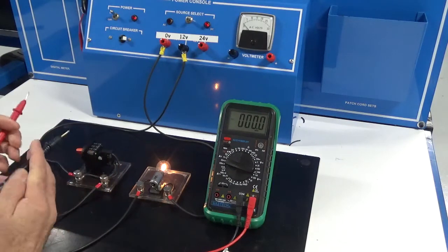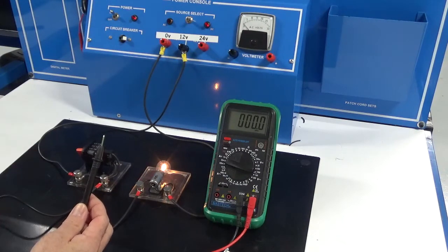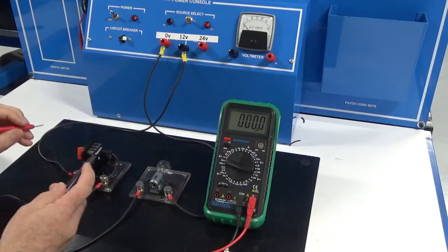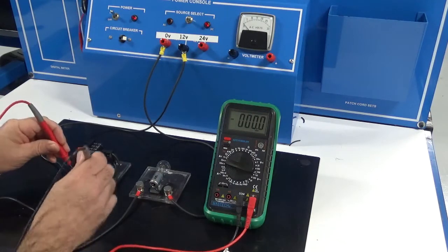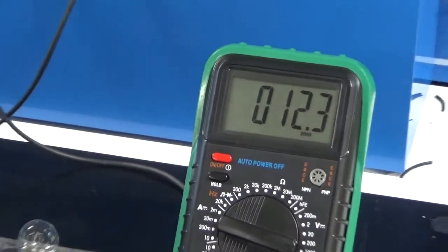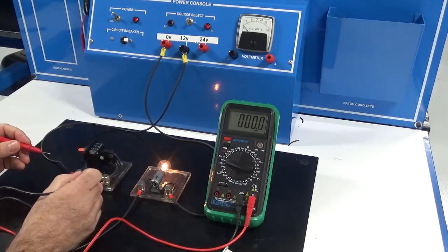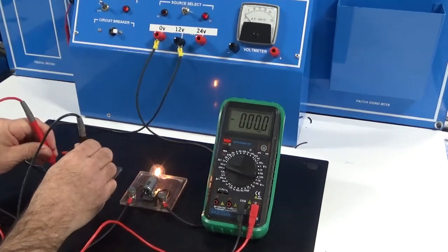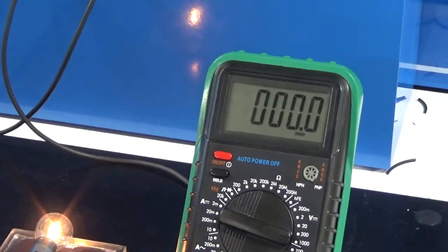The reason is the meter is actually displaying the difference in potential between where this lead is placed and where this lead is placed. With the switch open, there's actually a difference in potential. I have 12 volts on this side of the switch and 0 volts over here. So when I test it with my meter, it shows that difference in potential between those 2 points. When I close the switch, I now have essentially 0 ohms from here to here, so there is no difference in potential between this point and this point, and that is what my meter is showing me. I have 0 potential. But there's voltage present, we know that.